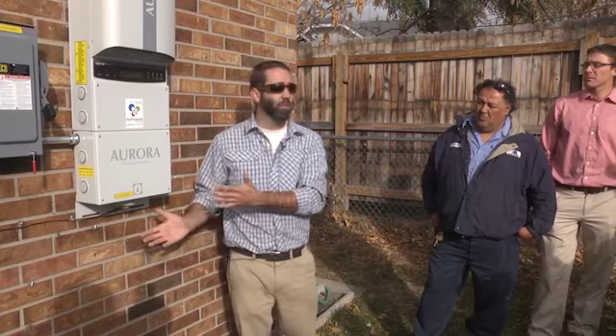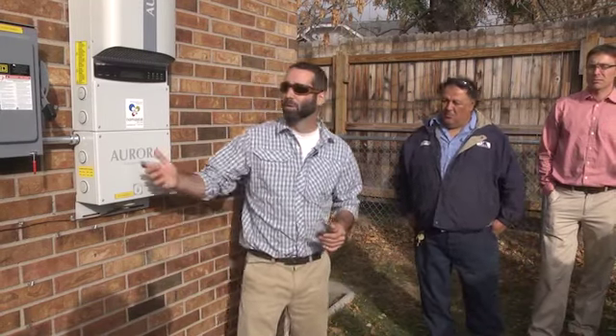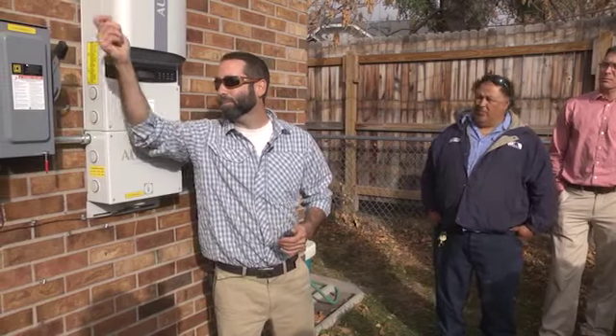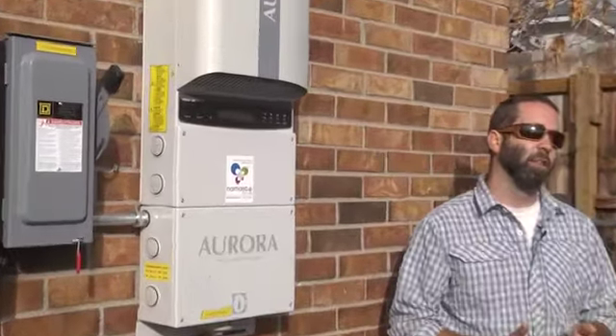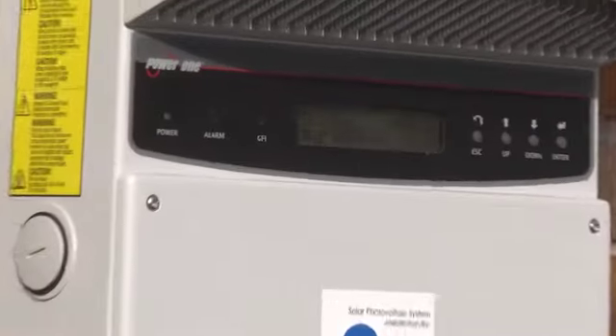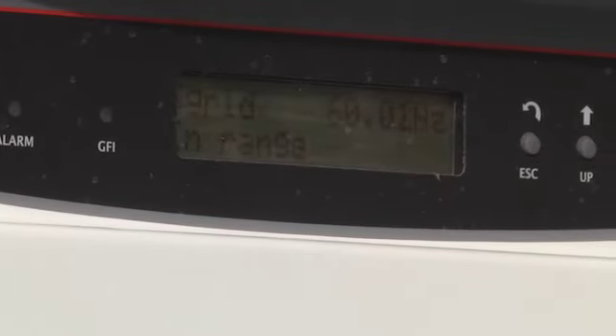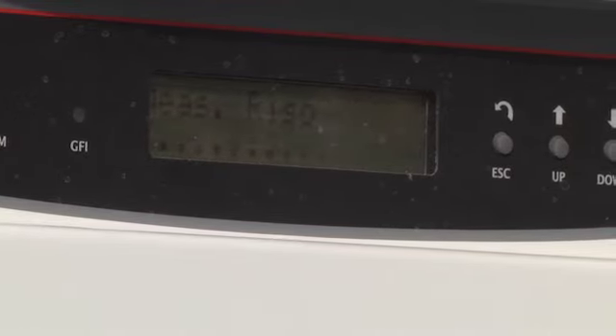So this is a very common situation you guys may see. So the easiest thing to do at that point is turn the AC disconnect back on. You hear it click. The inverter will then go through a 3 to 5 minute startup phase where it senses the grid voltage, it senses the grid frequency, and it makes sure everything is legit before it starts producing power. That typically takes 3 to 5 minutes. The Power 1s actually go a little bit quicker than that.